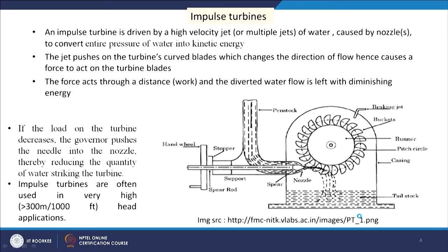Now we will look at impulse turbines. Water enters through the penstock and through a nozzle into the turbine casing. A governor can place a needle in the nozzle, so depending on the needle position the flow of water can change. The main feature of an impulse turbine is that it is driven by a high-velocity jet — or multiple jets — of water caused by nozzles. The nozzle converts the entire pressure of water into kinetic energy.